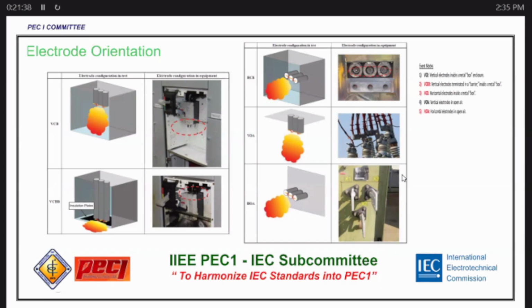And guys, the limitation here is the computation is from 208 volts up to 15 kV only. Why only up to 15 kV? Because whatever the result of their test, their equipment could only accommodate up to 15 kV. If it's 34, 69, 138 up to 230 kV, IEEE has no equipment to conduct that test.